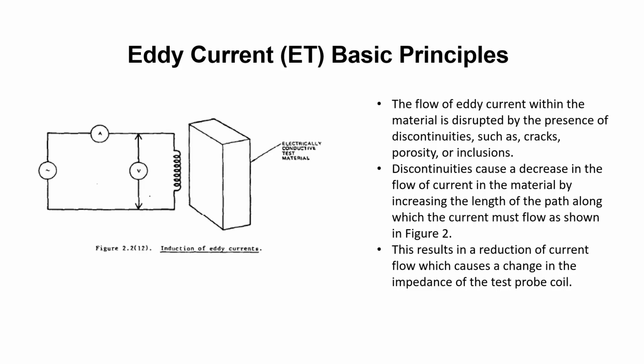Eddy current testing basic principles. The flow of eddy current within the material is disrupted by the presence of discontinuities such as cracks, porosity, or inclusions. Discontinuities cause a decrease in the flow of current in the material by increasing the length of the path along which the current must flow, as shown in Figure 2. This results in a reduction of current flow, which causes a change in the impedance of the test probe coil.